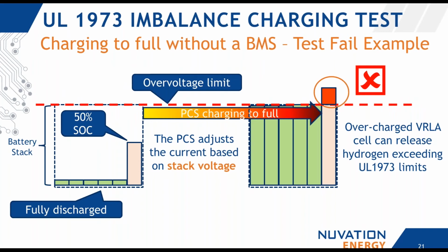This specific test, this charge imbalance test, has caught a lot of lead acid stack designers off guard. In addition to looking for thermal runaway conditions, the NRTL reviewer is also going to be looking for gases which an overcharged lead acid cell may produce. If we think back to the early lead acid systems used in telecommunication stations and UPS applications, it was pretty uncommon to see a BMS attached to that stack, monitoring each individual cell. Instead, the attention was given to manage the room. So you're evacuating any unwanted gases with proper ventilation and having sensors to set off alarms when the concentration becomes too large. But UL 1973 sets out a limit for that concentration of gas that can be generated from the stack. And so we're seeing a lot of new systems that require a BMS to protect their stack against that.